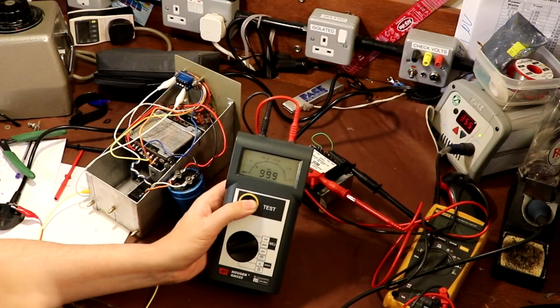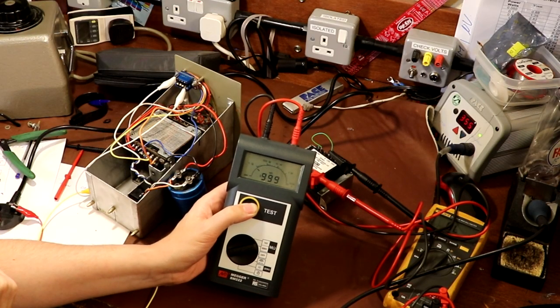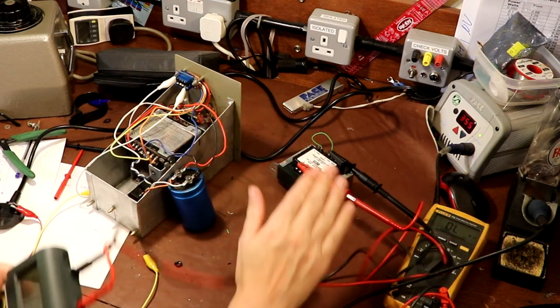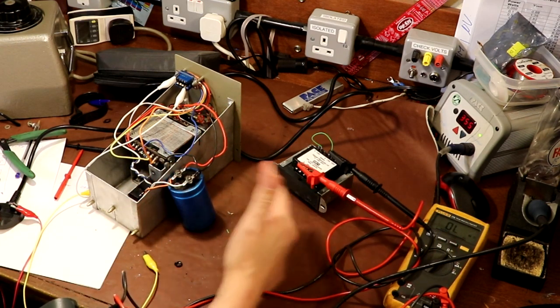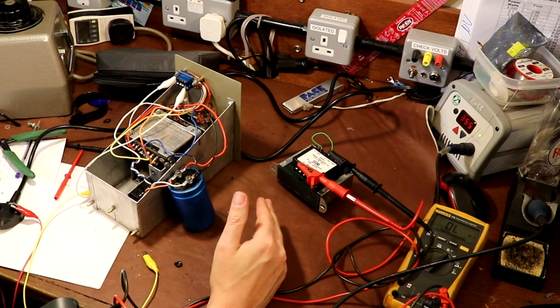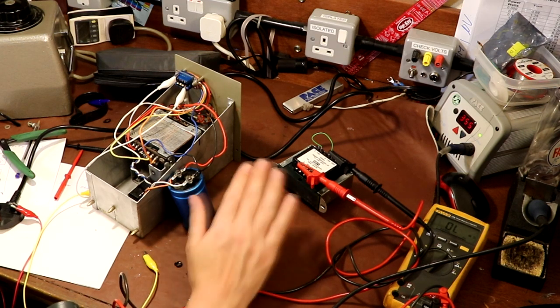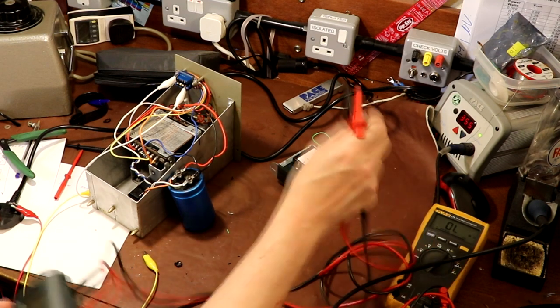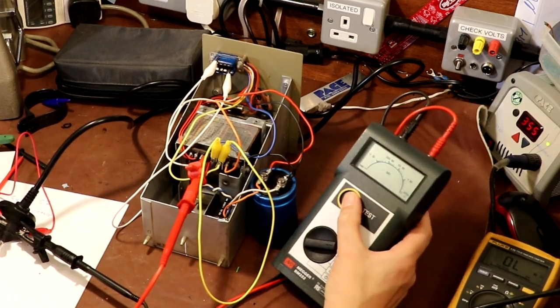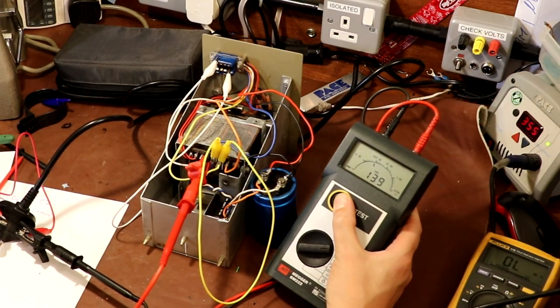999 megohms. So effectively that's 1 gigaohm, isn't it? 1 gigaohm of resistance. So there is absolutely no leakage between the primary windings and the secondary windings of this transformer. That's good. That's what I'd expect to see. And just press the test button, and that comes up.